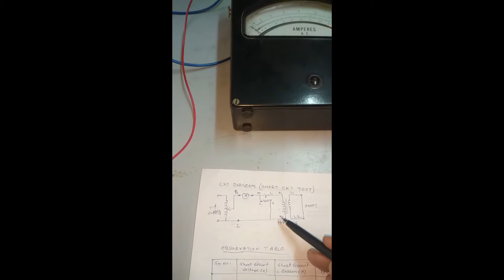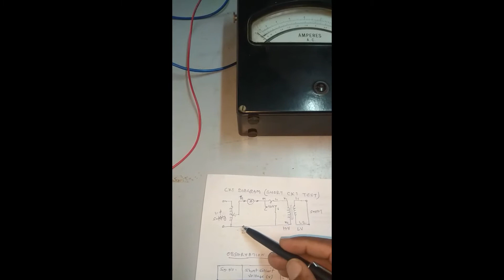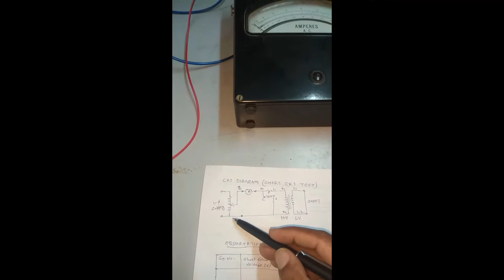From the line terminal of the wattmeter, that is connected to the first terminal of the HV winding, and the other terminal of the HV winding is connected to the V terminal of the wattmeter, as well as to the second terminal coming from the variac or dimmerstat. We are going to short M and C. Now let's do this on the equipment.